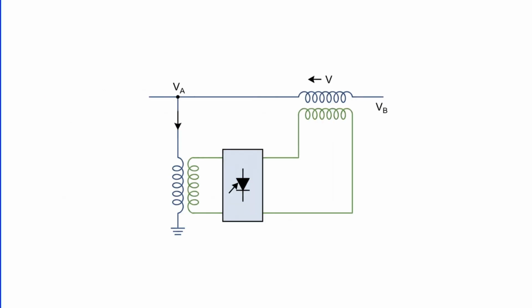The injected voltage is maintained perpendicular to the terminal voltage, and its magnitude is controlled using the Thyristor converter. The reactive power needed to generate this injected voltage is transmitted through the shunt transformer and the Thyristor converter to the boosting transformer. Why is this device so important?